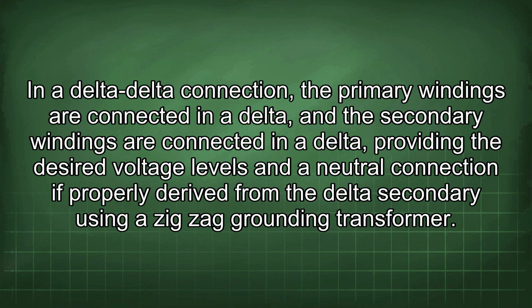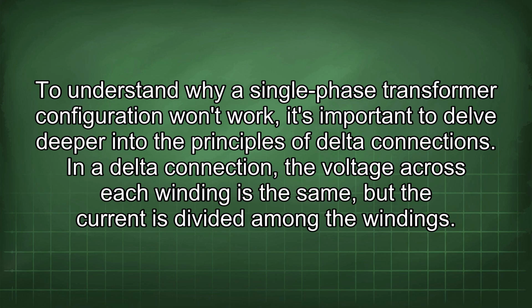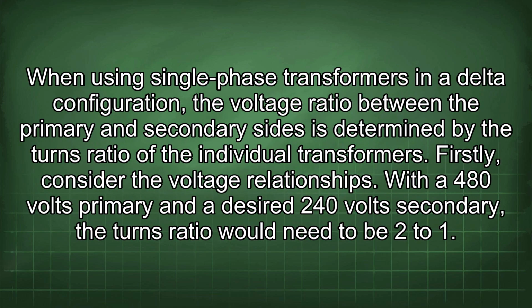In a delta-delta connection, the primary windings are connected in a delta, and the secondary windings are connected in a delta, providing the desired voltage levels and a neutral connection if properly derived from the delta secondary using a zigzag grounding transformer. To understand why a single-phase transformer configuration won't work, it's important to delve deeper into the principles of delta connections. In a delta connection, the voltage across each winding is the same, but the current is divided among the windings. When using single-phase transformers in a delta configuration, the voltage ratio between the primary and secondary sides is determined by the turns ratio of the individual transformers.